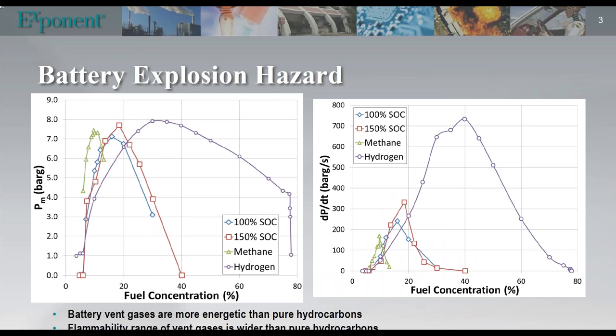To give you an idea of the hazard that could be posed by the gassing of a battery, Exponent did some testing a while ago where we charged lithium polymer batteries to 100% state of charge, SOC, and we also overcharged them to 150%. We took the gases and compared the maximum pressure in a 20-liter combustion vessel and also the dP/dt as a function of fuel concentration.